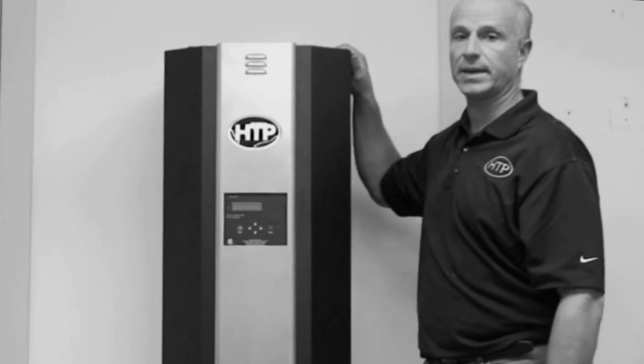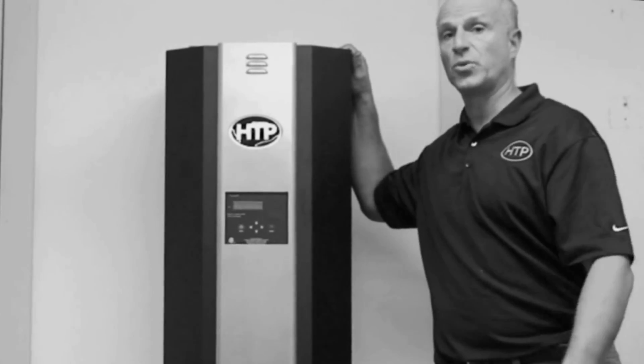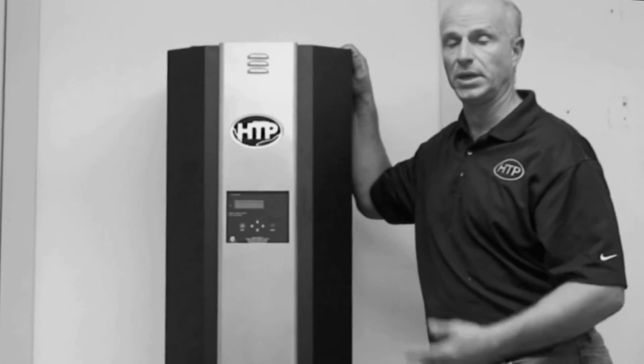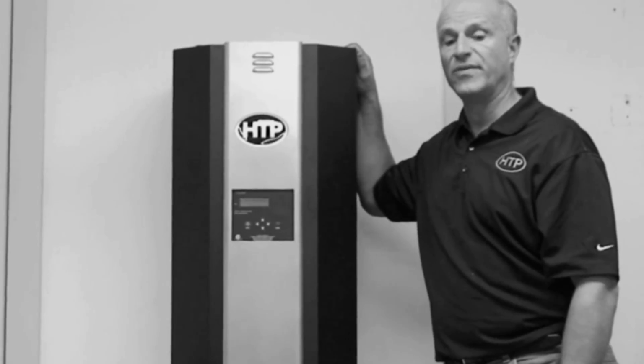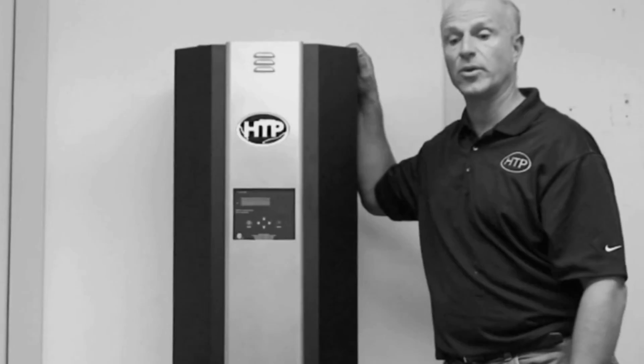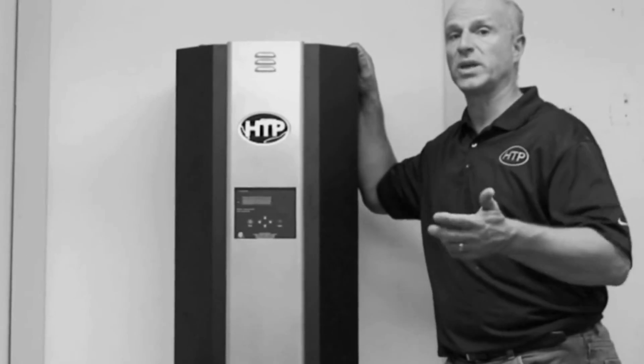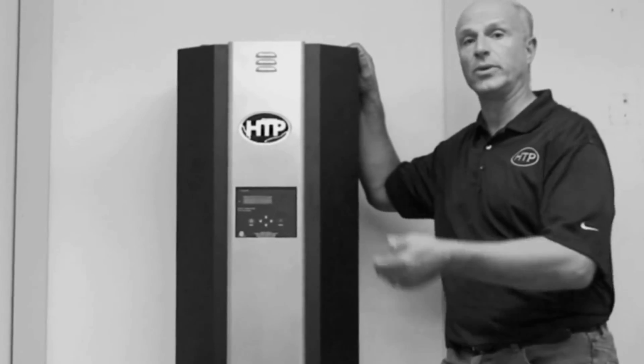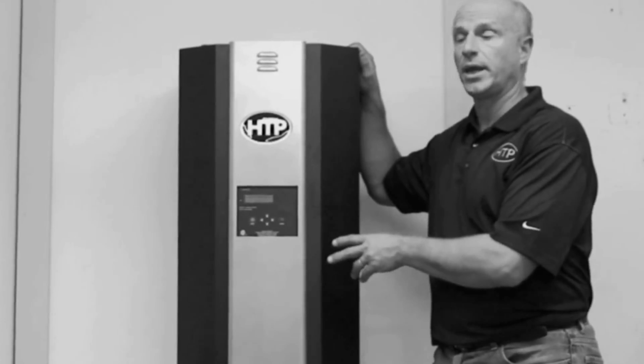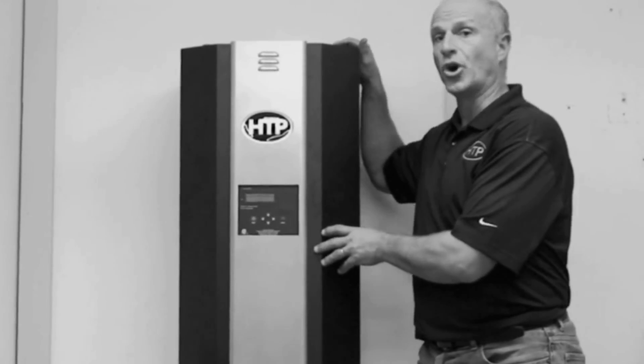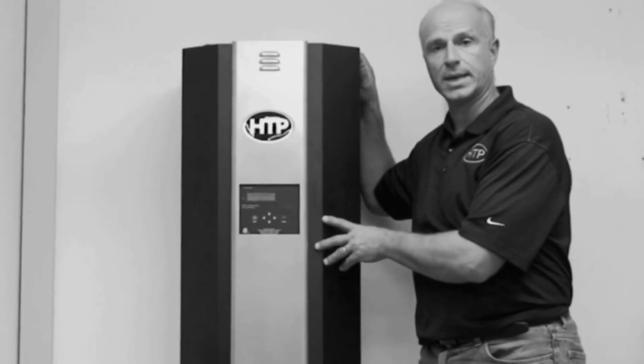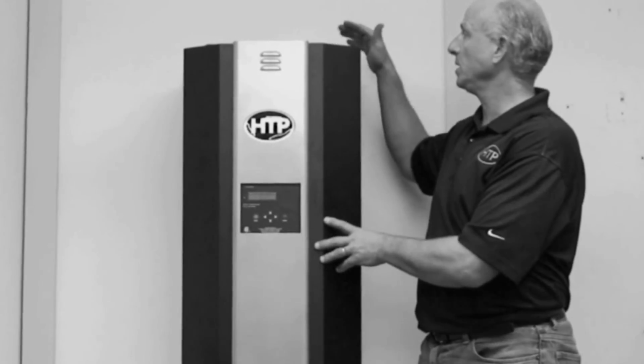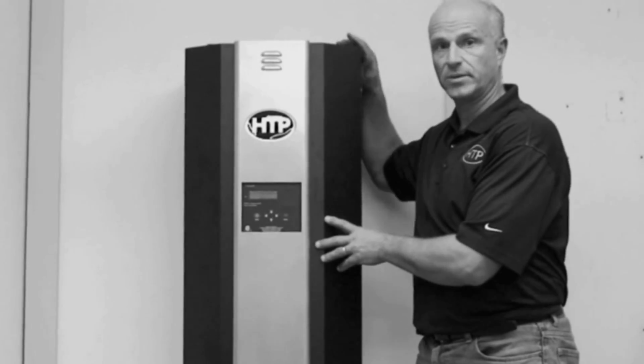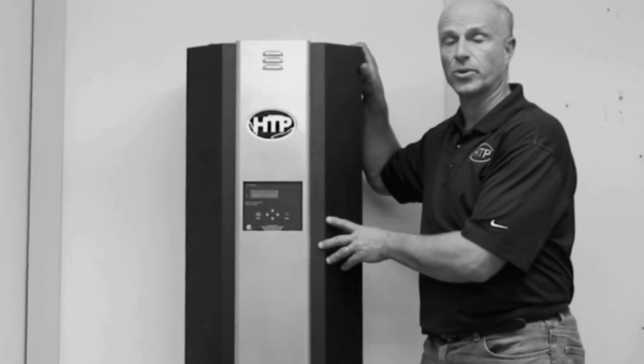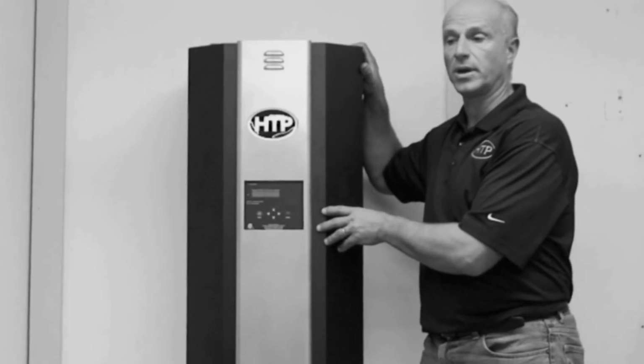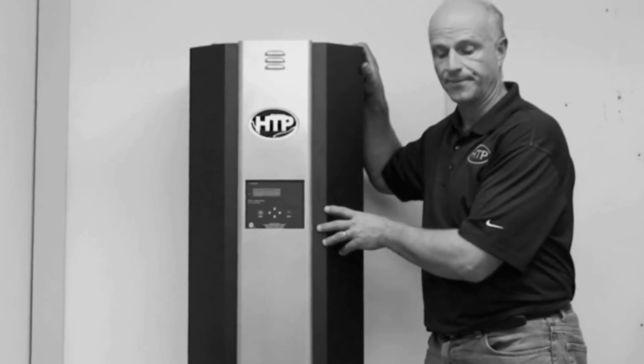Venting is very easy to connect up to 3-inch vent. We can go up to 200 feet combined on both the intake and exhaust. So venting the appliance and finding an area where to vent this, because we can go longer, helps a lot. If you're in a mechanical room and your pipes are located where you don't want to move them, which could cost a lot of money and a lot of time, our vents can be directed within the mechanical room or to an installation far away, which will help you out a lot.